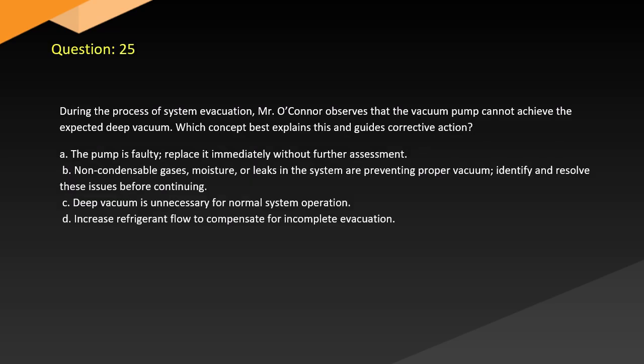Question 25. During the process of system evacuation, Mr. O'Connor observes that the vacuum pump cannot achieve the expected deep vacuum. Which concept best explains this and guides corrective action? A. The pump is faulty. Replace it immediately without further assessment. B. Non-condensable gases, moisture, or leaks in the system are preventing proper vacuum. Identify and resolve these issues before continuing.